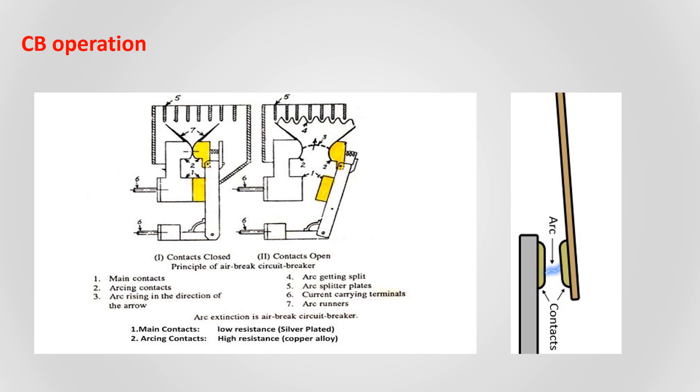If you see the diagram on the right hand side, the moving contact comes closer to the fixed contact. At the point of contact, arc is produced which may damage the contact. So in order to protect the main contact, we are using an arc contact. During closing operation, the arc contact closes first and then the main contact closes.